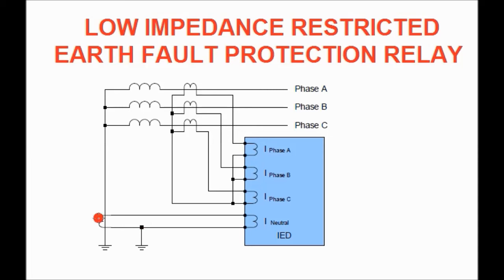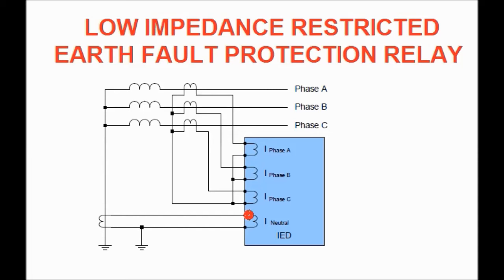Here the connection of the low impedance type restricted earth fault relay is shown. The neutral CT ratio is not the same as the bushing CT or phase CT ratio. The connection is simple: S1 terminals of the red, yellow, and blue phase CTs are taken respectively to the red, yellow, and blue phase coils of the relay, and the other terminals are shorted together to form the neutral and taken back to the CT junction box. Star formation is done in the CT JB. For the neutral CT secondary, S1 is taken to the neutral coil of the relay and the other terminal is taken back to S2.